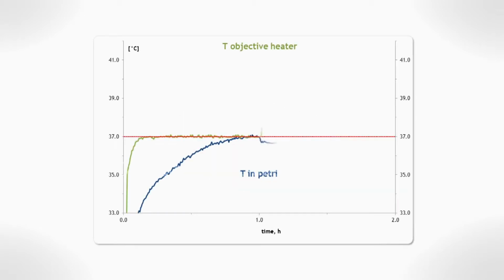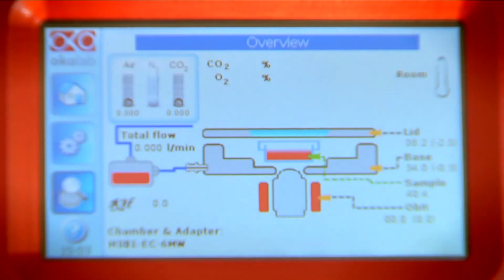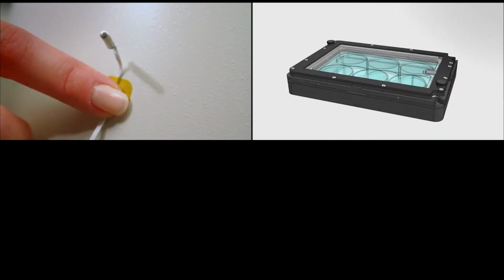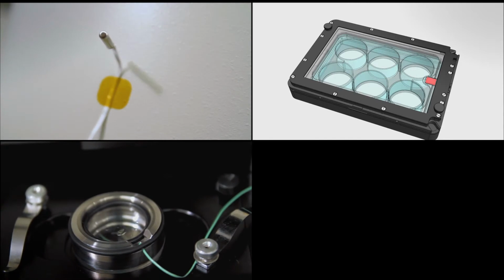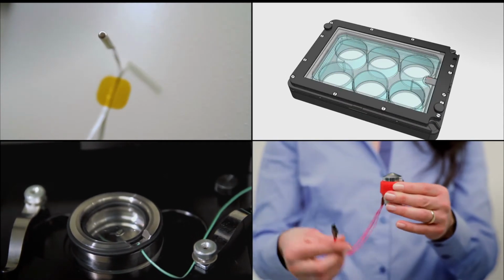The algorithm will progressively increase the temperature of the objective heater until the Petri reaches the set point temperature again. Calibration data can be stored as a function of room temperature and recalled when needed. In the overview page, the touchpad displays the temperature of the room, of the incubating chamber and lid, of the sample feedback sensor, and of the objective heater.